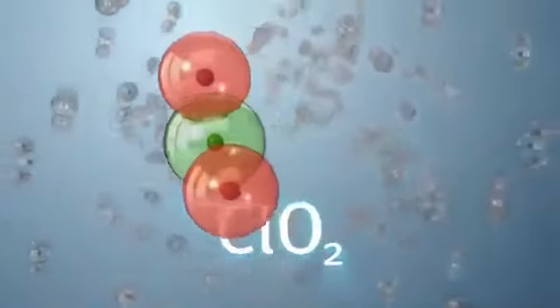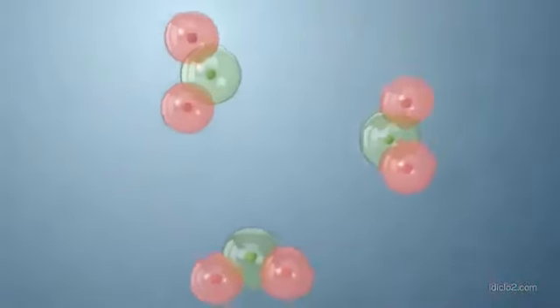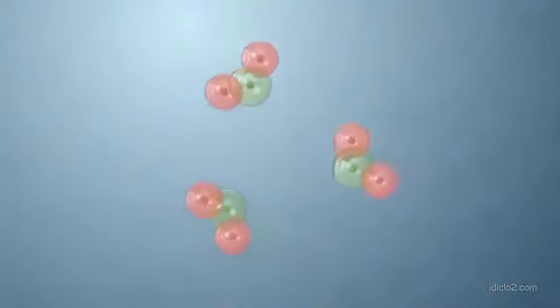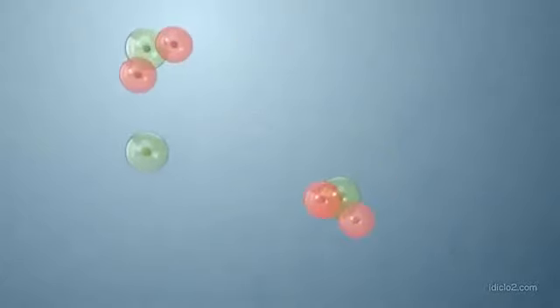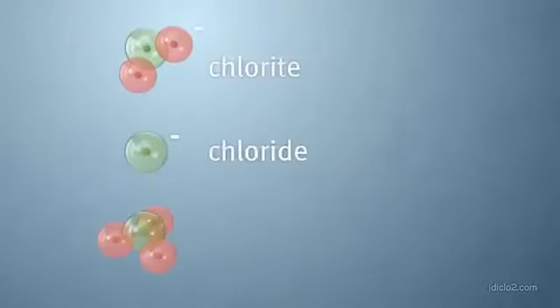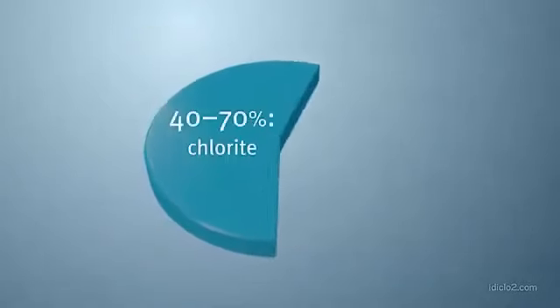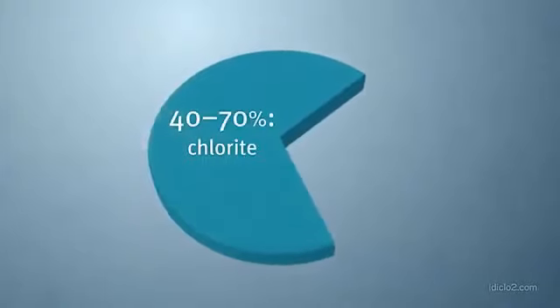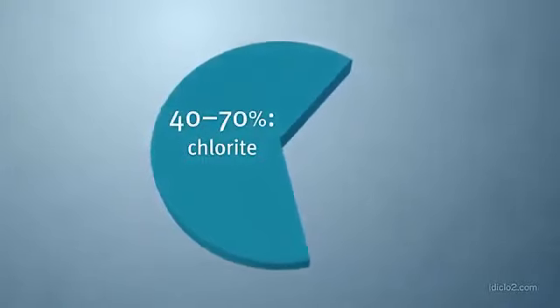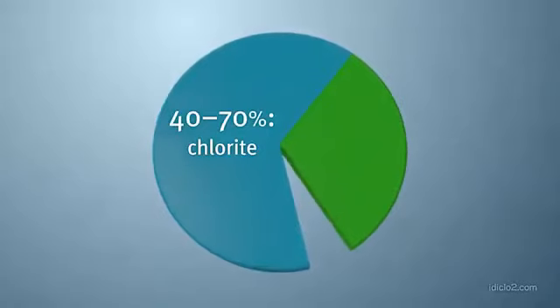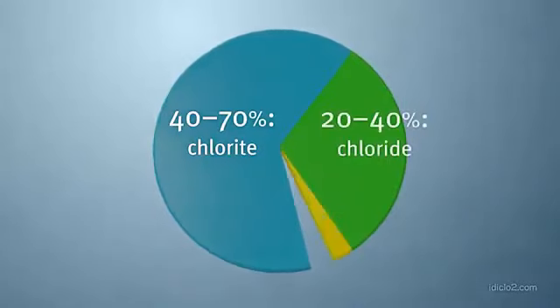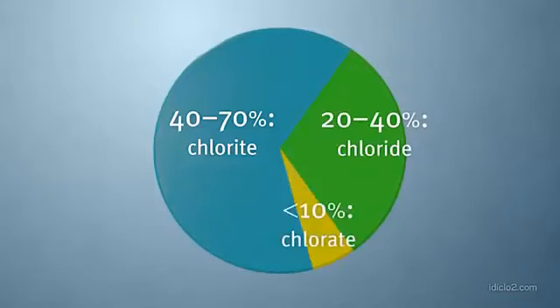Chlorine dioxide doesn't form chlorinated organics like THMs or HAAs. The decomposition byproducts of ClO2 generated by sodium chlorite include chloride, chlorite, and chlorate ions. Depending on the water makeup, approximately 40 to 70 percent of the applied ClO2 dosage will revert to chlorite ions. 20 to 40 percent of the applied dosage will convert to chloride, and less than 10 percent of the applied ClO2 will convert to chlorate ions.